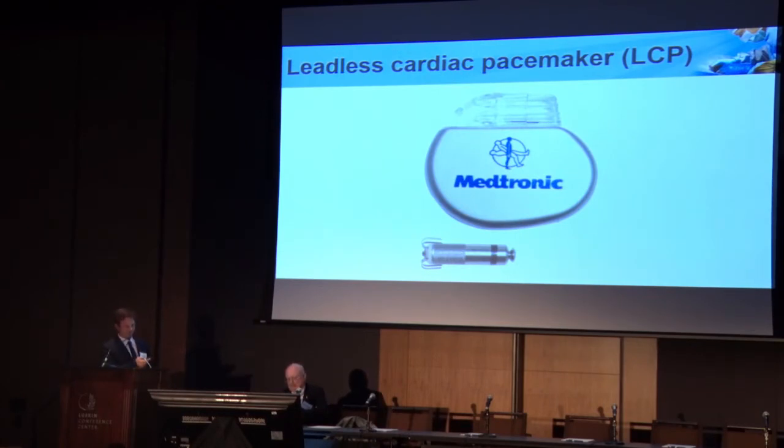This is the comparison of the device with the smallest Medtronic pulse generator, the Adapta S, and this is the Micra. It's actually a tenth the size of the current smallest device. And not only that, it contains the pacing function — the electrodes are built into this device, whereas you need a lead with the other one. So it's very compact and very versatile.